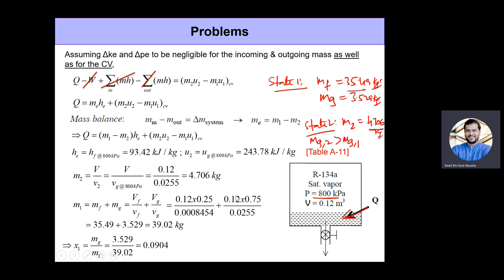And at state 2, we just have saturated vapor. So what we are saying is basically the mass of saturated vapor, which is simply the mass at state 2, is greater than the mass of saturated vapor at state 1. And this simply tells you that, as you're providing heat into the system, some amount of liquid got converted to vapor. That's it, nothing else happened. And because this liquid got converted to vapor, as you were trying to keep the pressure constant, you did not have to remove that liquid anymore, right? So instead of removing all 35.49, we removed a slightly lower quantity because we just did not have 35.49 kilogram of saturated liquid anymore. The mass of saturated vapor had increased to 4.706 simply because we had to heat up the refrigerant.